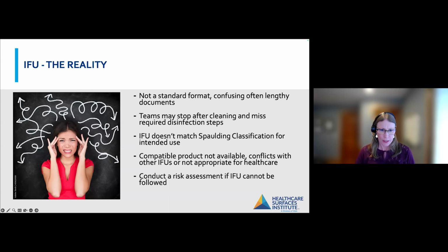And I kind of already talked about this a little bit, but sometimes the compatible products that are listed are not available. So if the piece of equipment was initially developed in another country and then it's being brought to the US to be used, we will not have access to that specific product regularly. And so that also puts you in a challenge. So oftentimes that requires the healthcare provider to reach out to the manufacturer to see if they have additional information that's not listed in their IFU about compatibility.